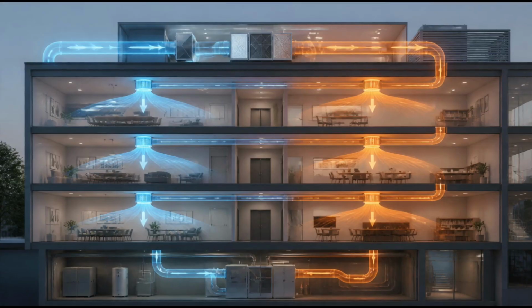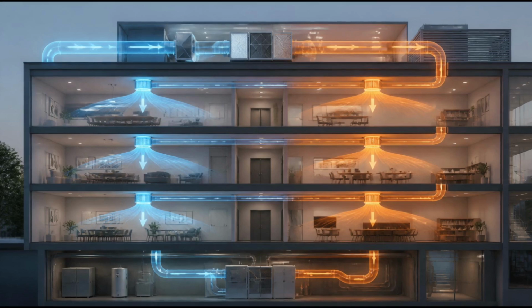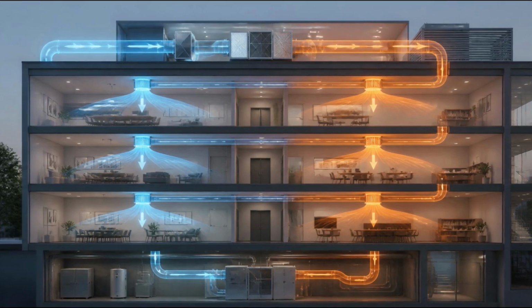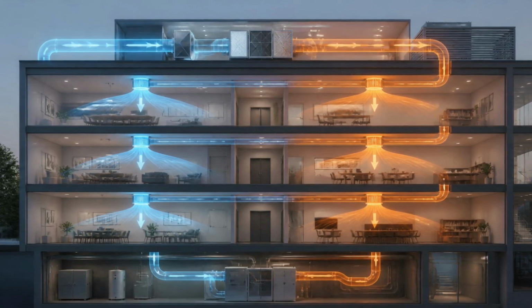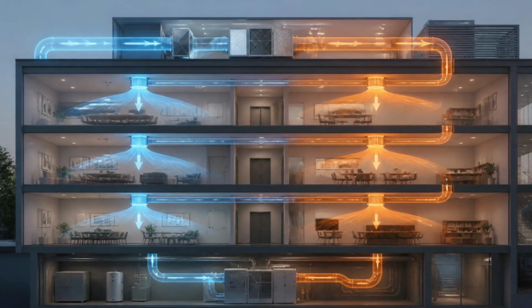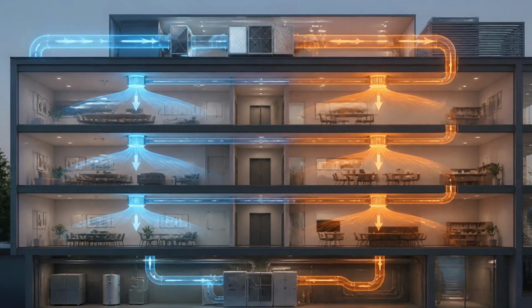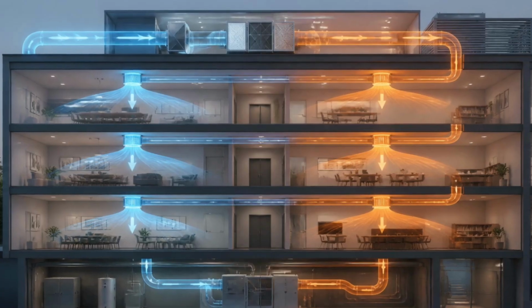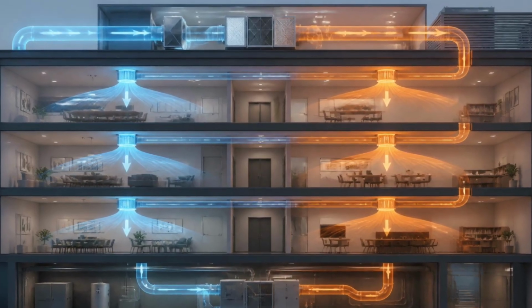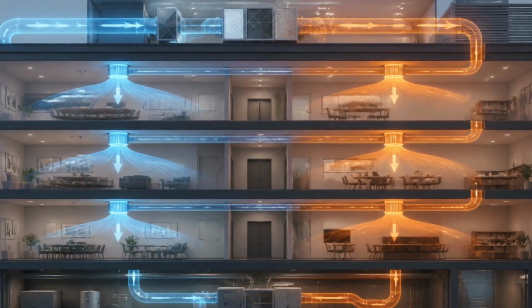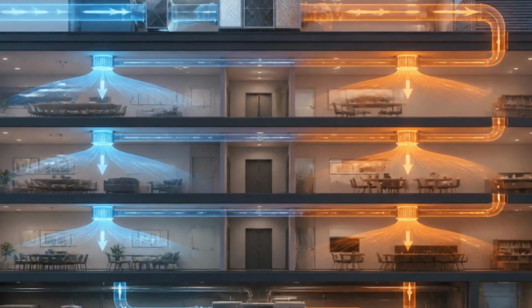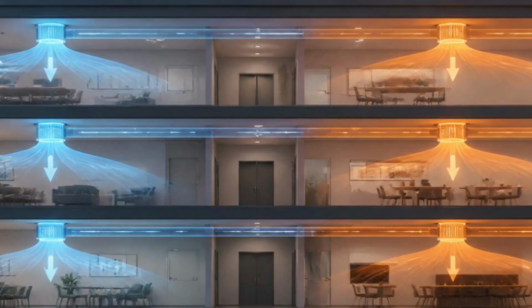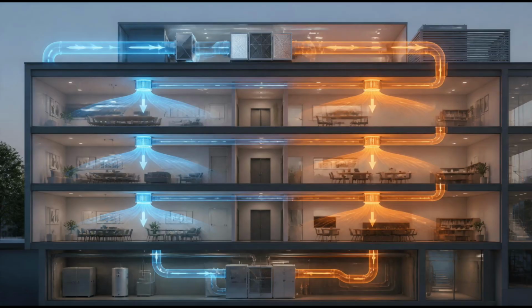Nighttime ventilation may continue in selected areas. Not every part of the building runs at reduced capacity during the night. Areas with continuous heat loads, server rooms, telecommunications closets, electrical switchgear rooms may require full or nearly full cooling regardless of the time of day. The building automation system knows about these zones and maintains appropriate conditions in them, even as it reduces airflow elsewhere.